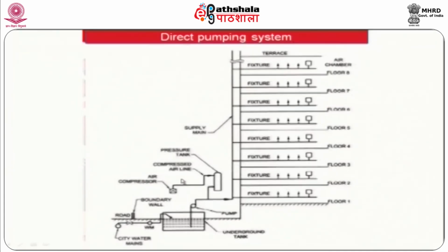So, this is the air vessel. There is a branch connected from the main at the bottom, and the air from the air compressor connected to the top. Here you have the vessel partly filled with water and the top with air. When there is a decrease in pressure, the water column will lower, and that will trigger the pump operation, and if there is need for air, the air will be supplied by the air compressor.